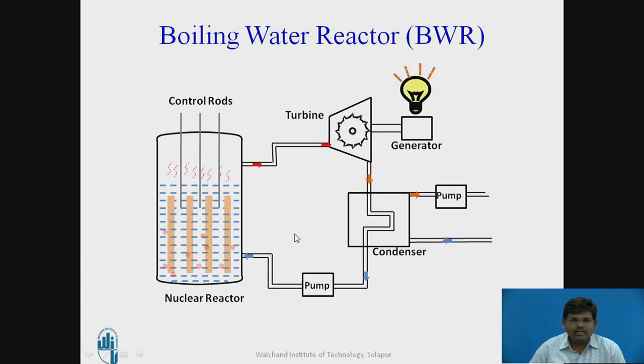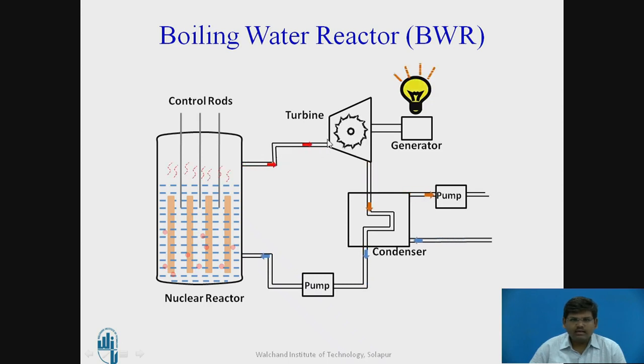There is no additional circuit provided in this — it is a direct circuit where water is directly converted into steam. The disadvantage of this type of boiling water reactor is that the water that directly comes in contact with the nuclear fuel is converted into steam and this comes in contact with the turbine. If maintenance of the turbine is to be carried out, the turbine also gets radioactivity affected. Thus, insulation needs to be provided from the reactor core to the turbine for safety purposes, which adds to the additional cost. So, all elements that come in contact with this steam get radioactivity affected.